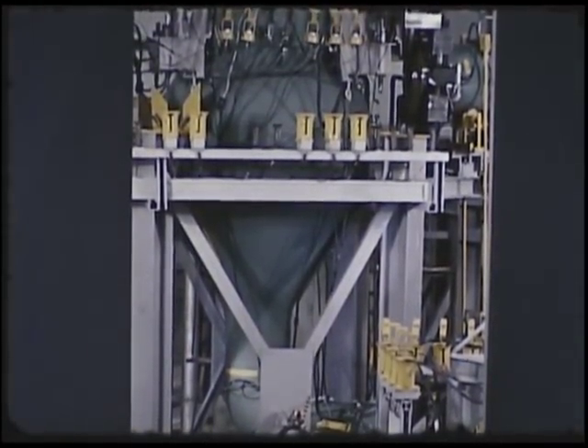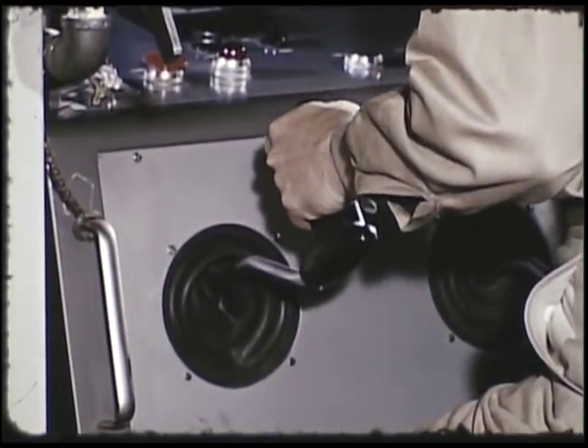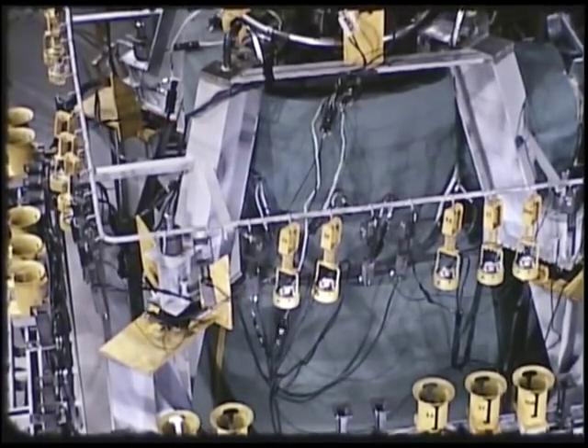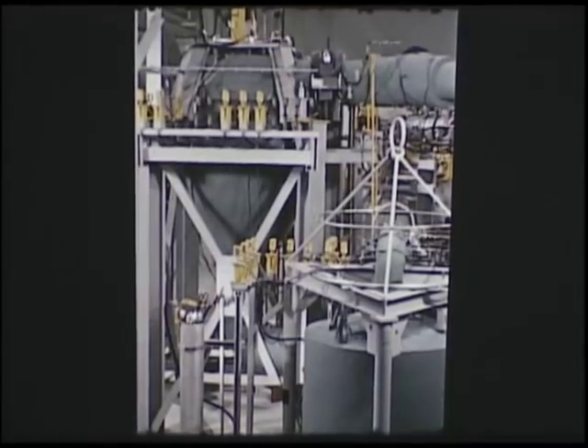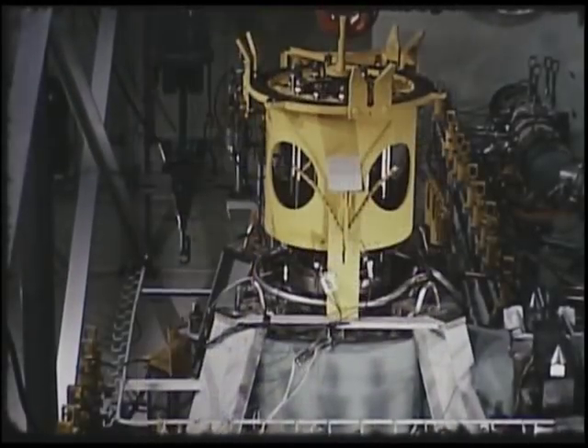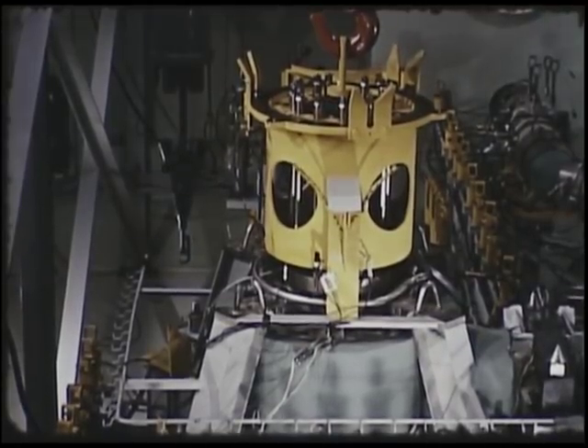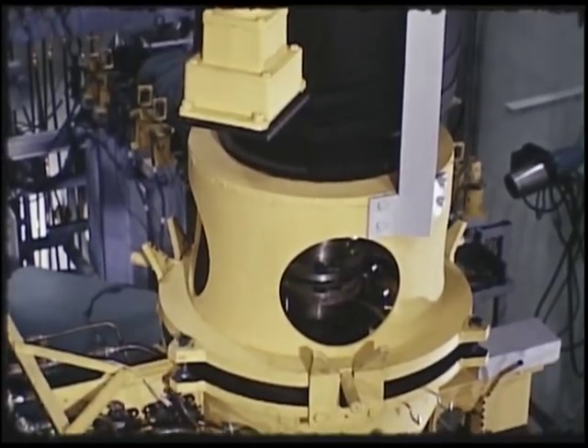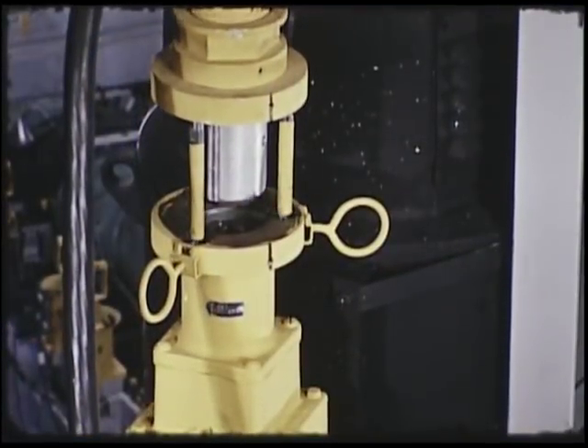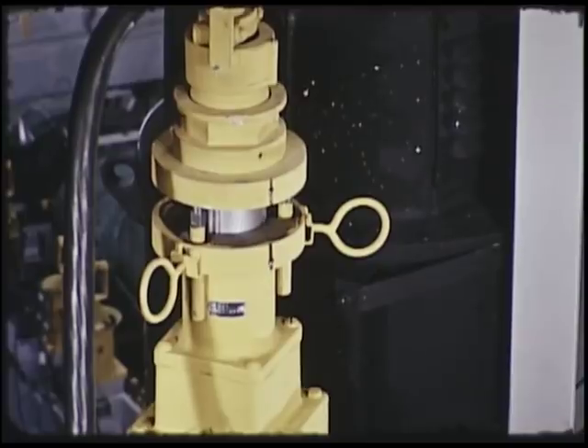Installation of a new or repaired reactor, pump, and motor is essentially the reverse of the removal of these components. Occasionally it is necessary to use the manipulator to assist the crane in positioning the reactor during installation. This operation, like the others, requires experience, care, and patience. Total time for removing and installing the reactor less pump is 24 hours. The replacement pump is lowered into position after the o-ring gasket is installed, followed by the new motor. This unit and the pump are connected by a self-guiding flexible coupling. After the hold-down bolts are tightened, the electrical connection is made. Removal and installation of the motor, pump, and reactor takes 36 hours.